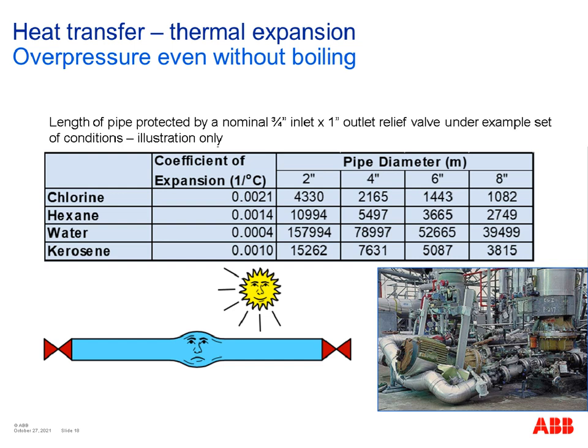On the photo on the bottom right-hand side of the slide there, we've got different situations. So this was in the case where a pump was running with blocked-in pipe work. So the pump was imparting energy to the system every time the fluid moved through the pump, and that resulted in the material, the process stream, actually heating up gradually, and eventually you had overpressure, and that caused the severe damage you see in the photo. And in this case, the fluid was ethylene oxide, so not really something you want to be taking any risks with. So that caused quite a lot of damage.